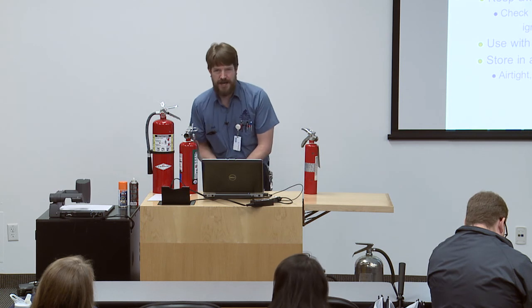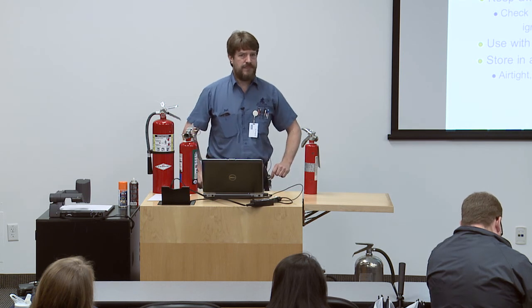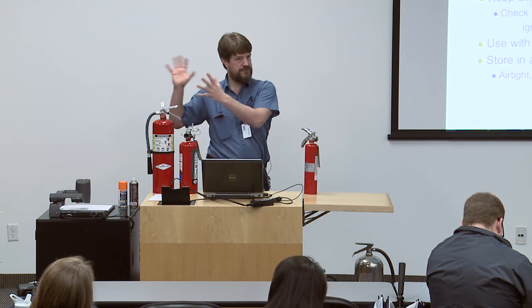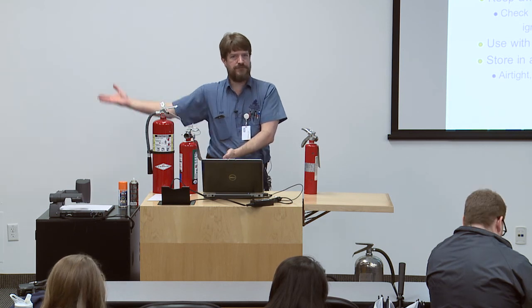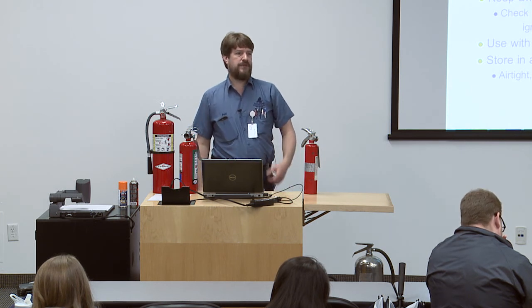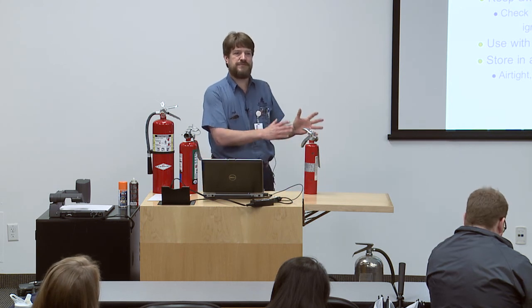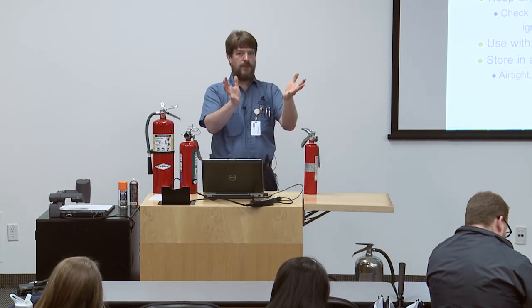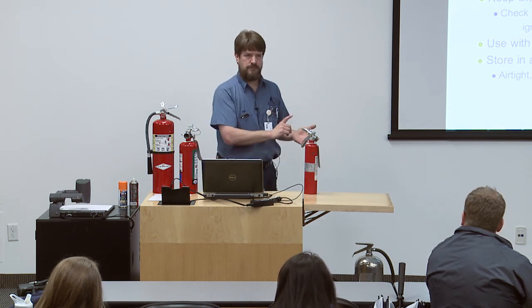We had this issue over at Swiss Tower. The fire inspector came by and said, this says electrical room on it. Well, that's because when we first put the building up, we were going to put the electrical stuff in there. So it said electrical on it. And she says, if it says electrical, even if there's no electrical equipment in there, it's an electrical room and you have to move all of your storage out. Well, the other side said storage, but it had a bunch of electrical equipment in it. So she says, well, you can store non-combustibles in here as long as it's 30 inches away in all directions from whatever the electrical source is, the mechanical source. Stay 30 inches away and non-flammable.